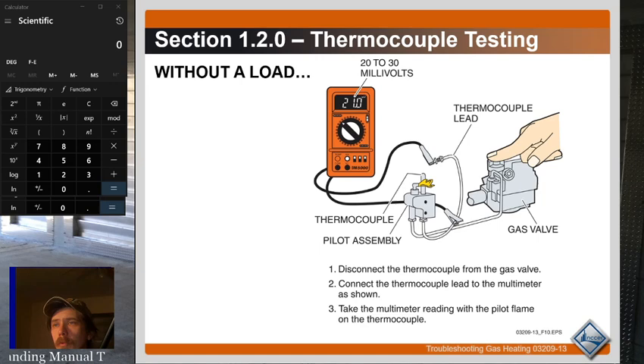Testing a thermocouple. So if you think you've got a bad thermocouple, remember a thermocouple is going to be on a standing pilot. So the most common thing you'll troubleshoot a thermocouple on is a water heater or a boiler. But water heaters are extremely common. A regular gas water heater is about 60% efficient, and it generally uses a standing pilot on the burner system. So if you have a standing pilot, then you generally will have a thermocouple to prove, or it can also be called a thermopile if it's a little bit bigger. That proves that the flame's on.